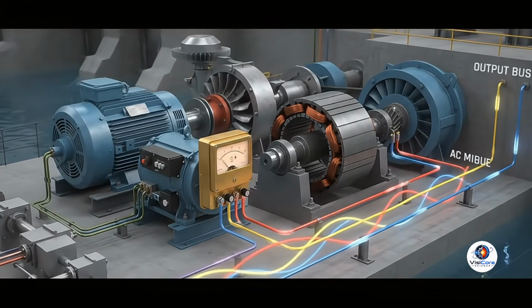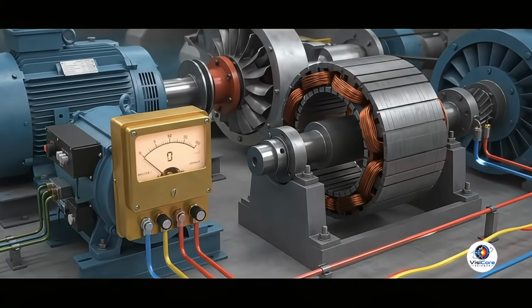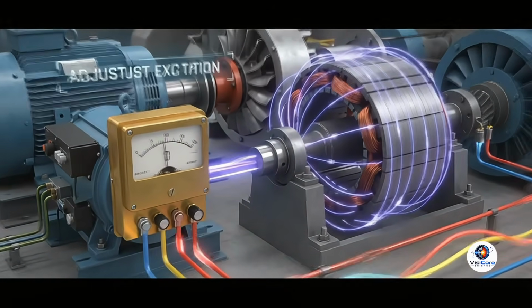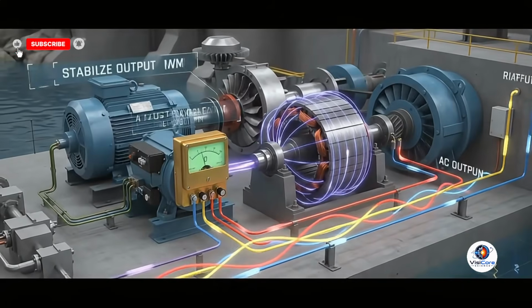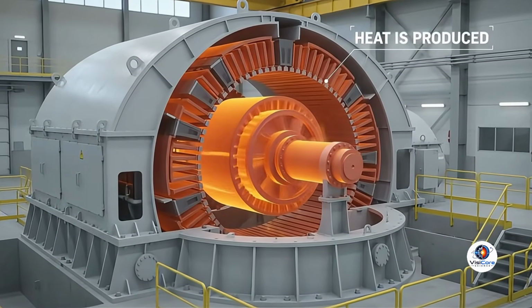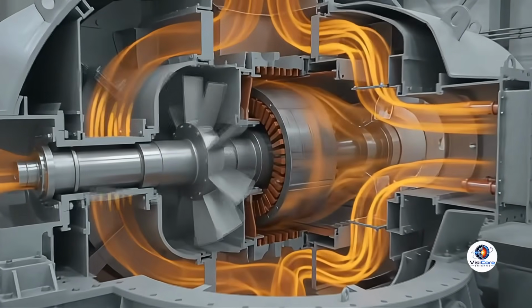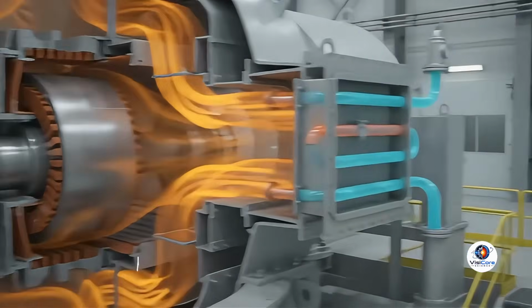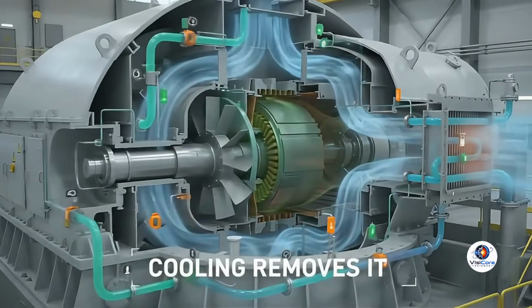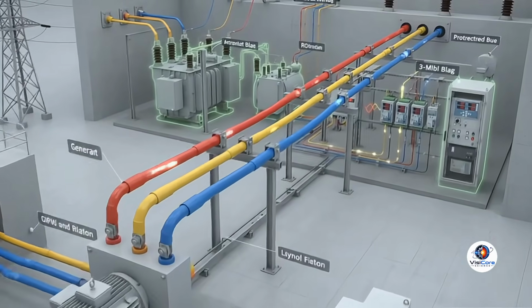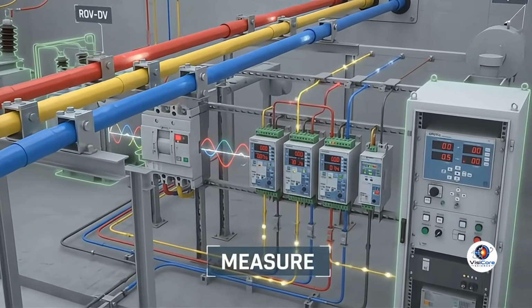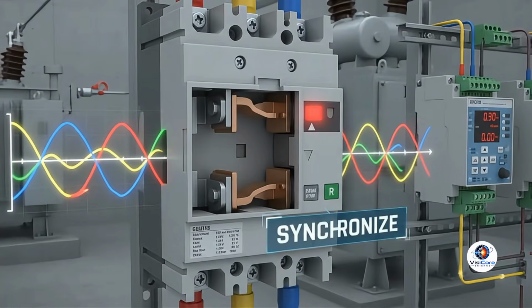An automatic voltage regulator adjusts rotor excitation. Changing magnetic field strength helps maintain the generator's electrical voltage. Electrical resistance, magnetic losses, bearings, and airflow friction produce heat. Internal ventilation and water-cooled heat exchangers remove it. Before connection, protection systems confirm that generator voltage, frequency, and phase match the electrical network.